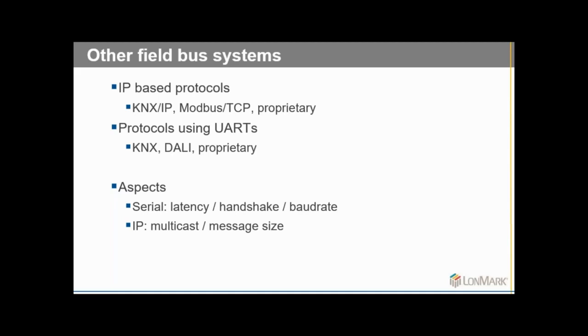So when I've been talking about RS-485, what you can't do is tunnel BACnet MSTP via HD-PLC. That will never work - we don't tunnel handshake signals on HD-PLC. That won't work. If you are working on IP, you have to deal with message sizes - they shouldn't be too small because then it becomes inefficient. And you have to deal with unicast and multicast addressing. So those are the key aspects if you want to port yet another fieldbus system on HD-PLC.